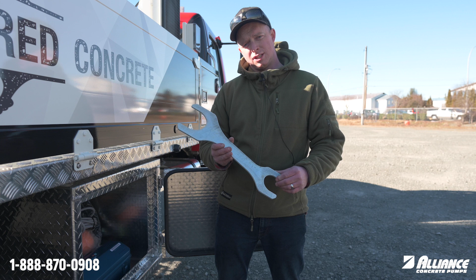One thing I want to touch on is this wrench here. It comes with every one of our concrete pumps, and a lot of people don't know what it is. This is a wrench for your suction screen inside your hydraulic tank. When you go to change your hydraulic oil and clean your tank, you want to remove your strainers — the large strainer is for the main oil suction, and the small strainer on some units is used for the boom filter, or the boom suction for the boom pump.